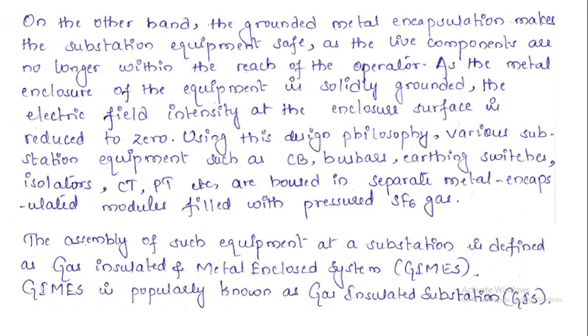On the other hand, the grounded metal encapsulation makes the substation equipment safe. Whatever enclosure or envelope we are using for the gas insulated substation will be grounded. The grounded metal encapsulation keeps the equipment safe, as the live components are no longer within the reach of the operator. As the metal enclosure is solidly grounded, directly connected to the ground potential, the electric field intensity at the enclosure surface is reduced to 0. So there is no shocking action, no chance of getting shocks. So the operator is safe.